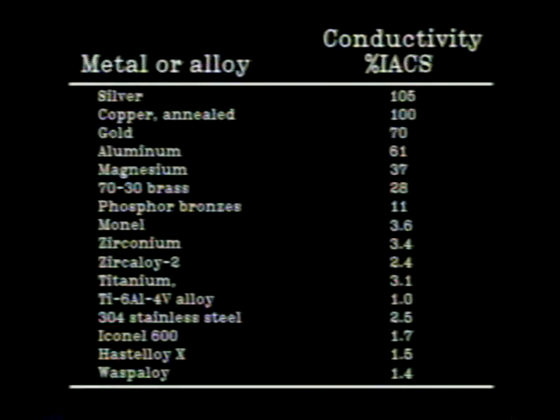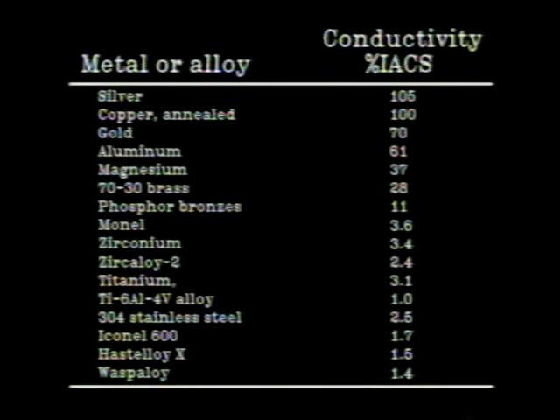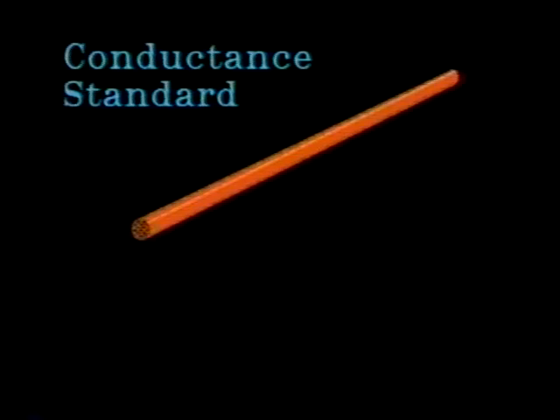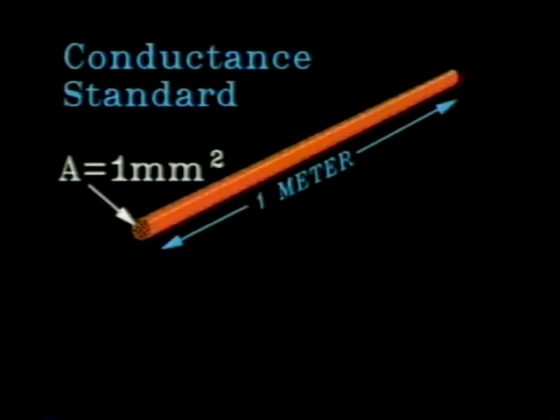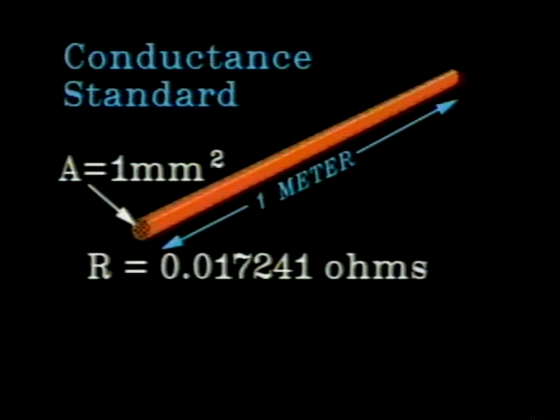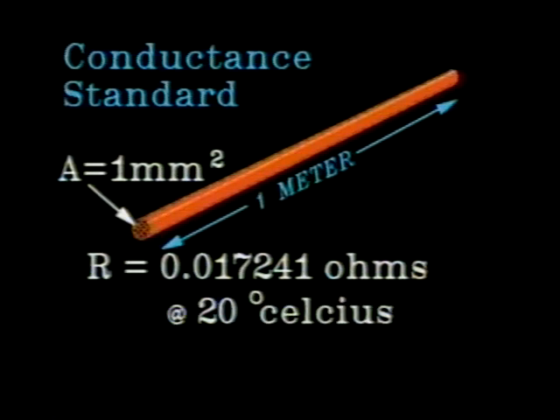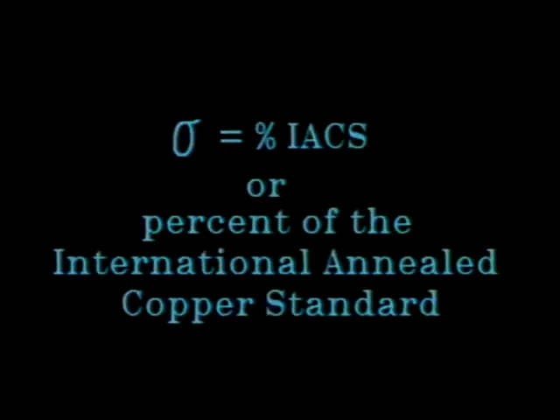In eddy current testing, instead of describing conductance in absolute terms, an arbitrary unit has been assigned, since the relative conductivity of metals and alloys varies over a wide range. The need for a conductivity benchmark is of prime importance. In 1913, the International Electrotechnical Commission established a convenient method of comparing one material to another. The commission established that a specified grade of high purity copper, one meter in length and having a uniform section of one millimeter squared measuring 0.017241 ohms at 20 degrees Celsius, would be arbitrarily considered 100% conductive.